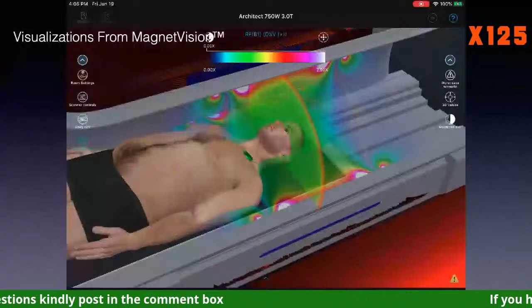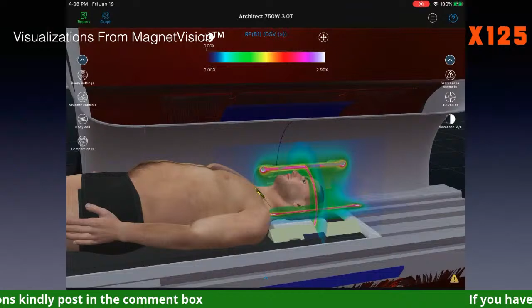And as I switch back and forth and change the view, you can appreciate just how much more constrained the RF energy deposition is between these two coils. And one more time, I'll see if I can restart that illustration. And we go back and forth between body coil for transmit and a local transmit-receive coil. And as you can see, that makes an enormous difference in the amount of tissues that are potentially exposed to radio frequency energy.